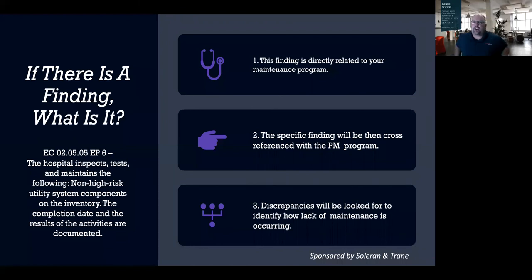Now there is another nuance to this. If you're in an area like Clayton was talking about, like in the South, you're actually going to consider this a high risk utility system component on your inventory. And when you're doing your annual assessment, that's actually going to be rated higher than everybody else. But typically the chiller is identified on the non-high risk utility system components. So make sure that when you're doing your assessment, you're taking that into perspective based upon your geographical area. Anybody in the South, anybody in Arizona, that's going to be higher, and you might consider it a higher risk utility system component just based upon your geographical area and what type of weather you're getting all the time.